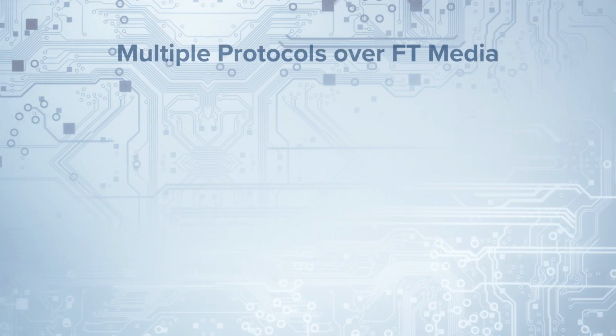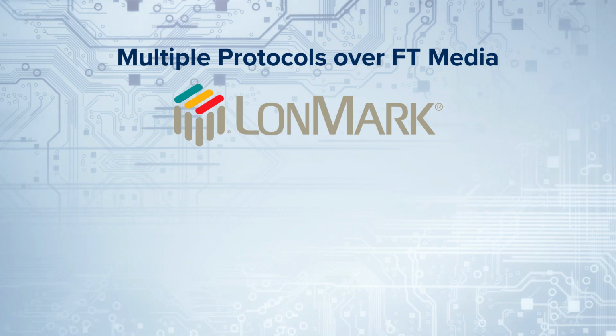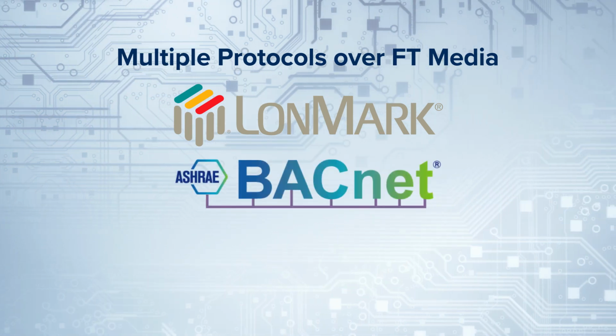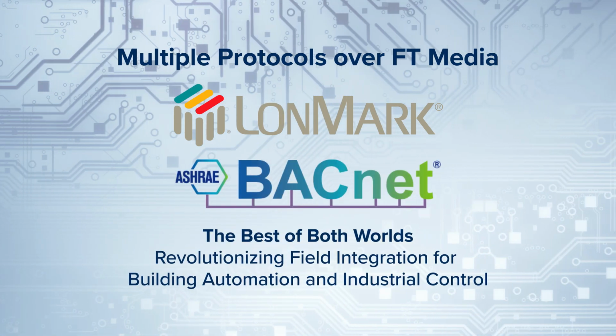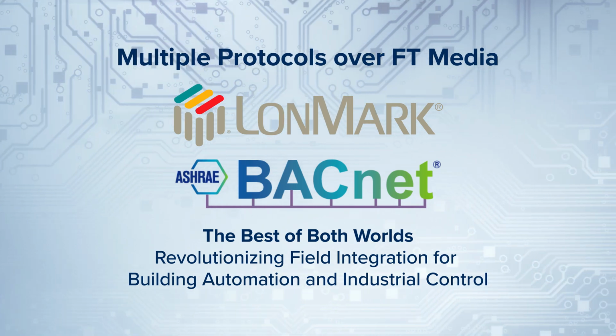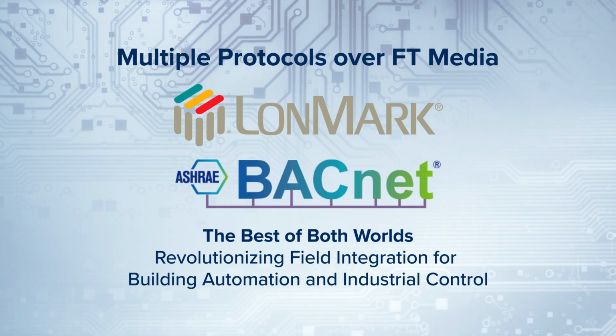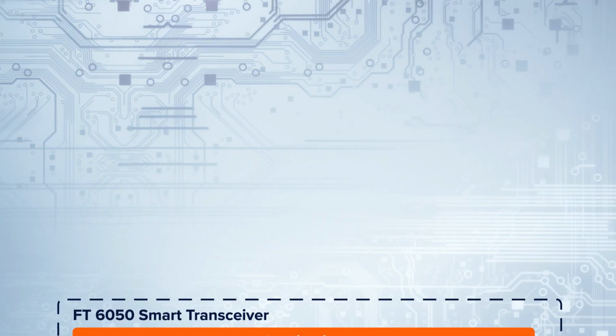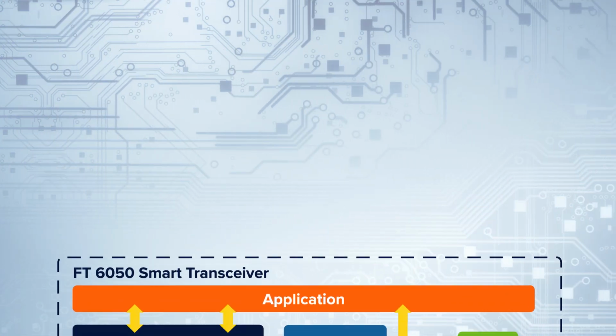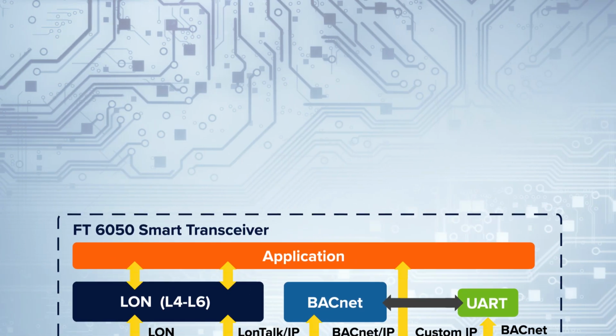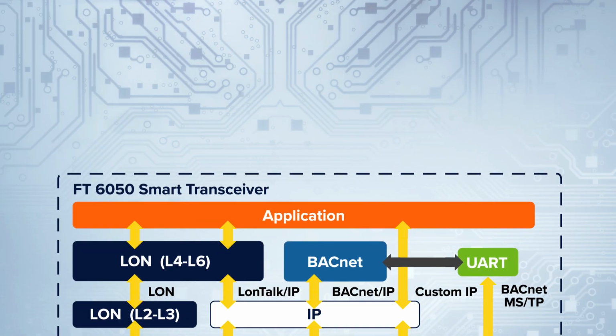Originally developed for LON networks, FT now natively supports BACnet and custom messaging, so multiple protocols can communicate simultaneously over the FT channel. BACnet FT is a native implementation of the standard BACnet stack on top of Adesto's FT technologies. What's important to understand is BACnet FT is simply a new data link, and the rest of the BACnet stack is completely standard. BACnet FT is also scalable.